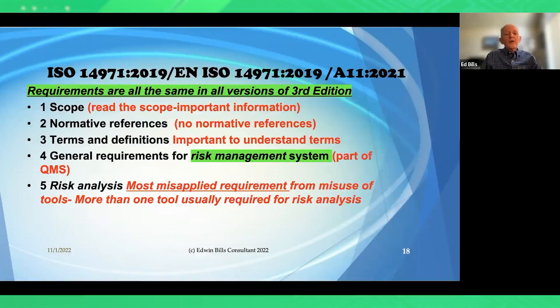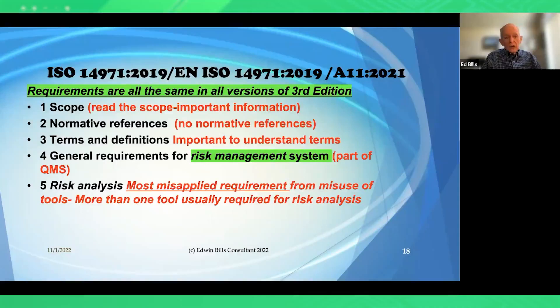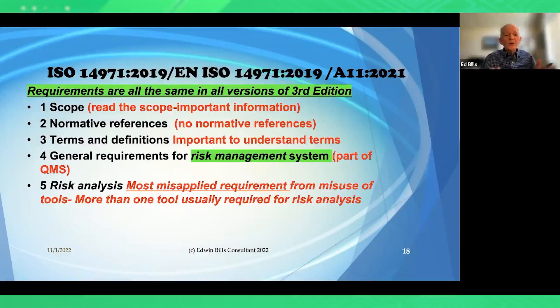All requirements are the same across all versions of the third edition. Read the scope — people often don't, but it contains important information. It clarifies that ISO 14971 is not a business risk standard, not a project risk standard, and does not cover clinical risk, which is the clinical decision-making made by the healthcare provider. The standard tells users the risk of using the device; healthcare providers then assess the patient and determine if it is the right device — ISO 14971 does not tell them how to make that decision.